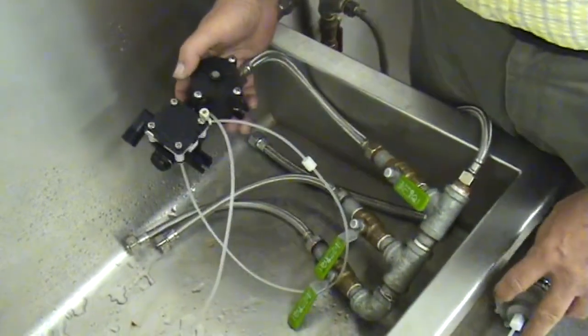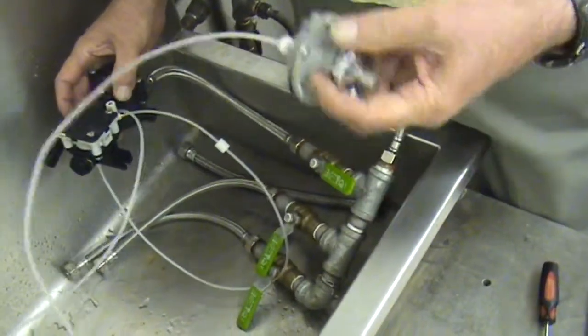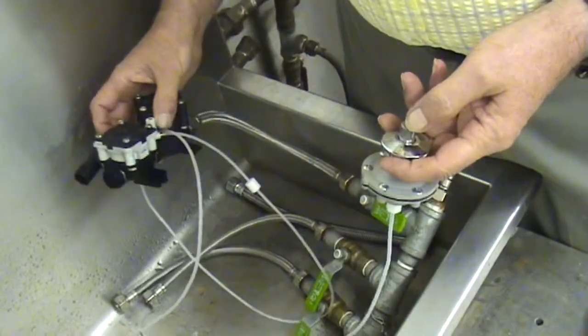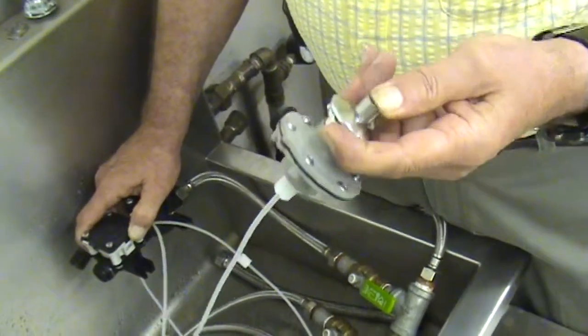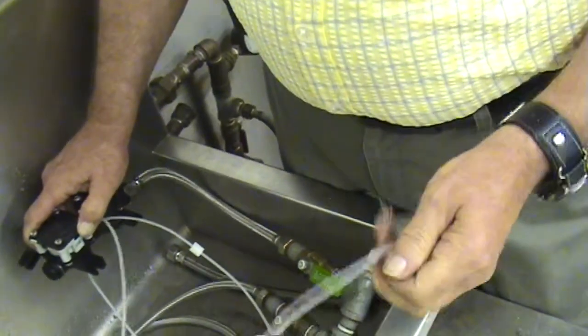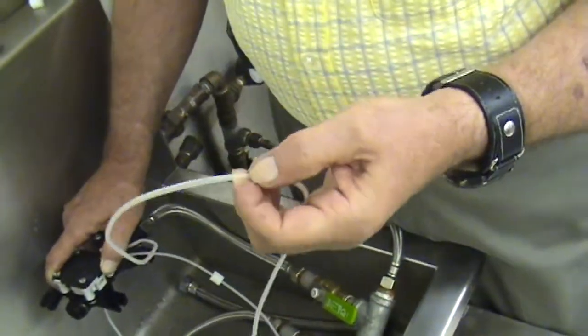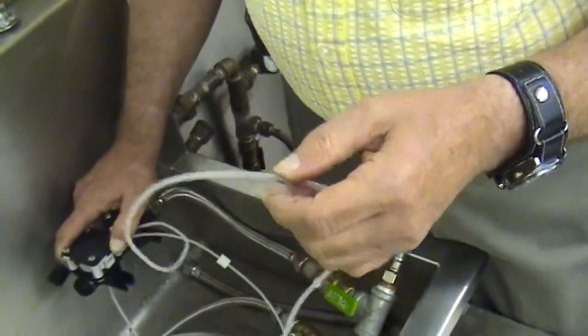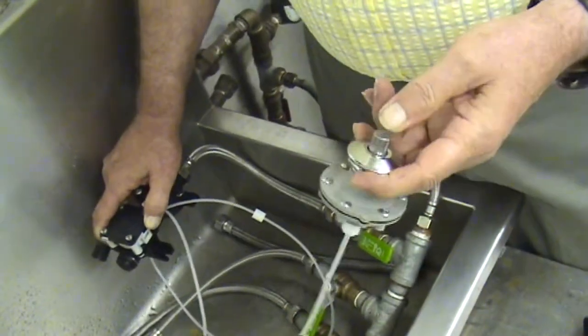Now sometimes you'll get into a situation where you have a push button that's kind of spongy and hard to push. If that's the case, you want to check your tubing. Make sure that your tubing is not kinked or pinched shut because a spongy button is an indication of that problem.